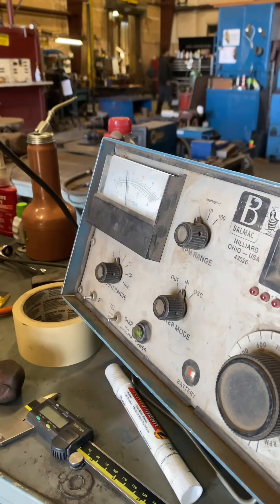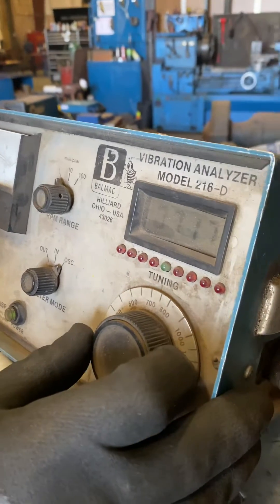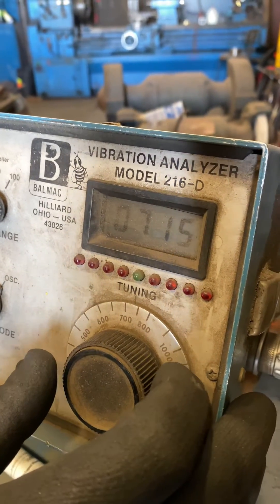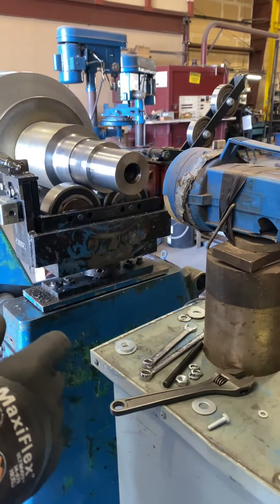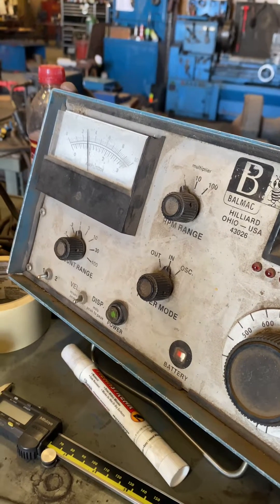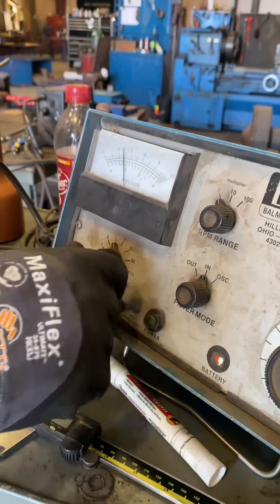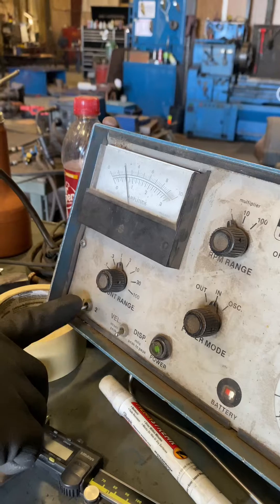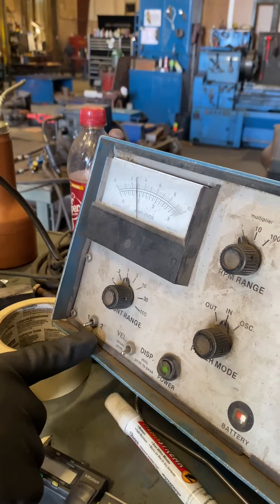We had a phase change as well — we were at 4:15 and now we are at 2. We are 3 tenths of a mil. I want to try and get it down a little bit lower. We're under a quarter of a mil on the drive end, and we are 3 tenths of a mil on the opposite drive end.